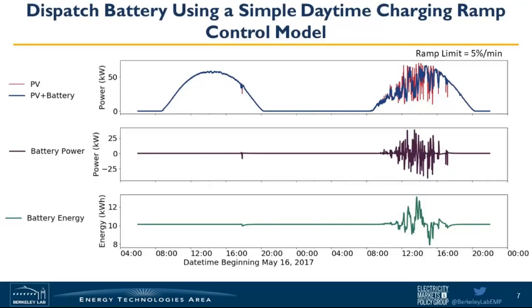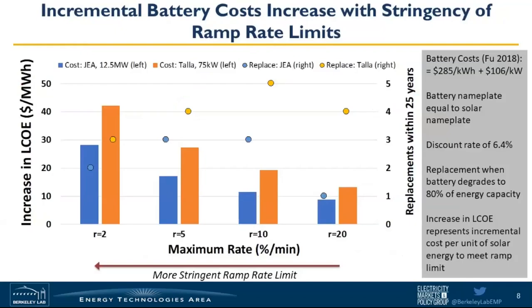Now, note that the battery that's needed for this is very short duration. In this case, only a 15-minute duration battery would be needed to meet this 5% per minute ramp limit. We then used this control algorithm and a simple rule of thumb for sizing the battery needed to meet increasingly stringent ramp rates. The more stringent the ramp rates were, the longer and longer duration batteries were required to meet them.